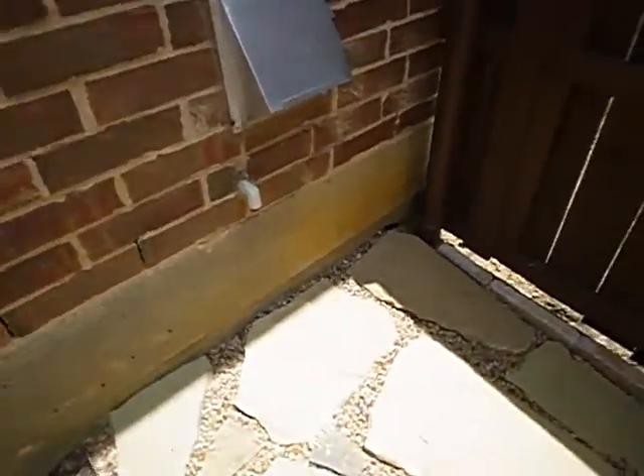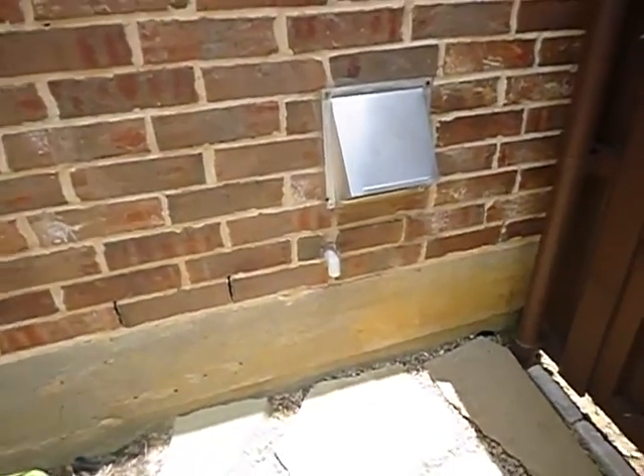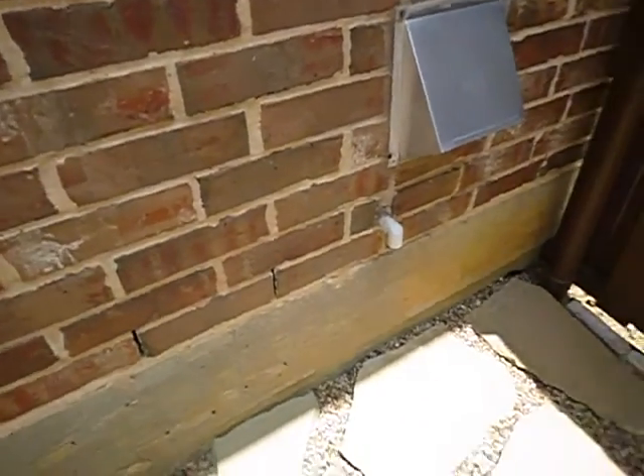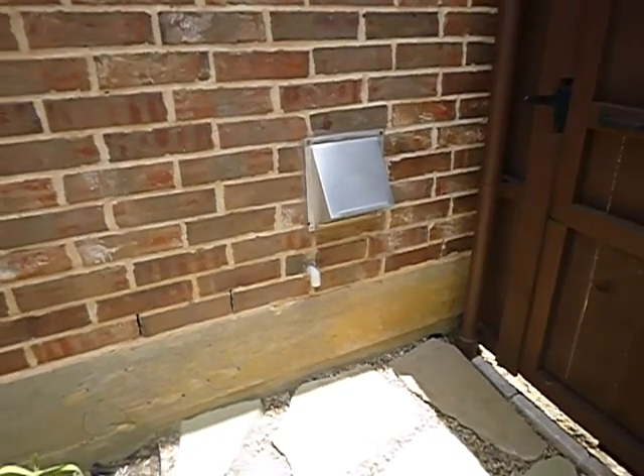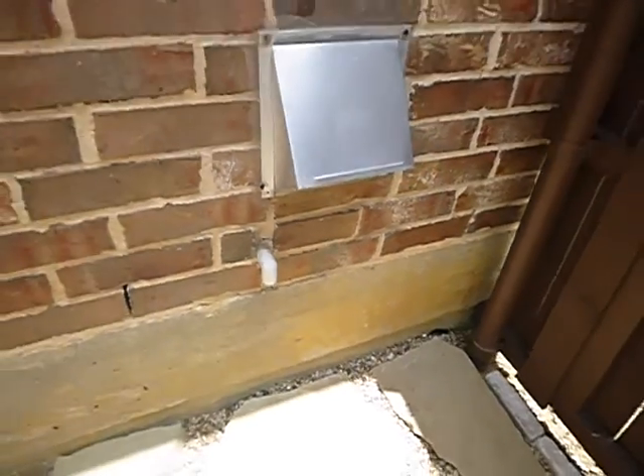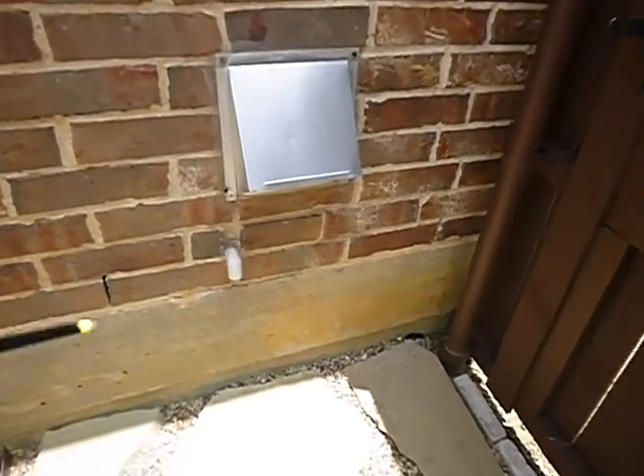Okay, we've had a little bit of foundation repair here or something, right in there. Now this is interesting, because I can't find the water heater temperature pressure relief valve drain line terminations, but this is right about where the water heater is. That would be for these safety pans. Some people think you can't, but you can commingle water heater safety pan drains. You can't commingle temperature pressure relief valve drains. Regardless, let's assume that I'm right for the moment: it's not supposed to be any farther from the ground than 6 inches. Not supposed to be closer than 3, but no farther than 6. So this drain line is too high if it's what I think it is.